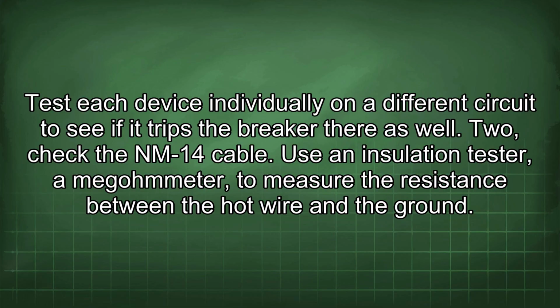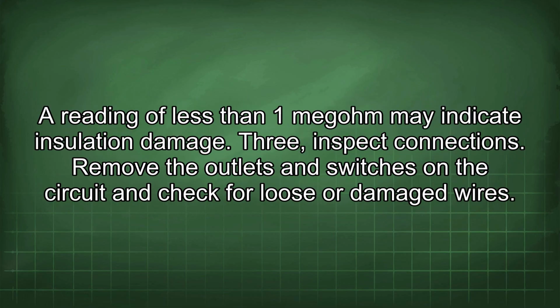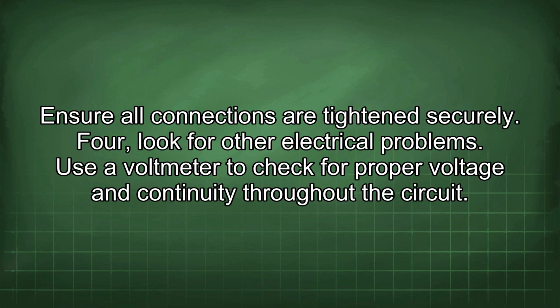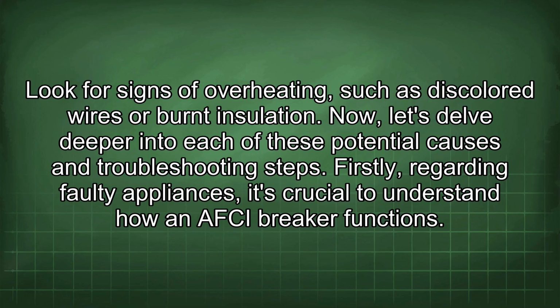2. Check the NM-14 cable. Use an insulation tester, a megohmmeter, to measure the resistance between the hot wire and the ground. A reading of less than 1 megohm may indicate insulation damage. 3. Inspect connections. Remove the outlets and switches on the circuit and check for loose or damaged wires. Ensure all connections are tightened securely. 4. Look for other electrical problems. Use a voltmeter to check for proper voltage and continuity throughout the circuit. Look for signs of overheating, such as discolored wires or burnt insulation.